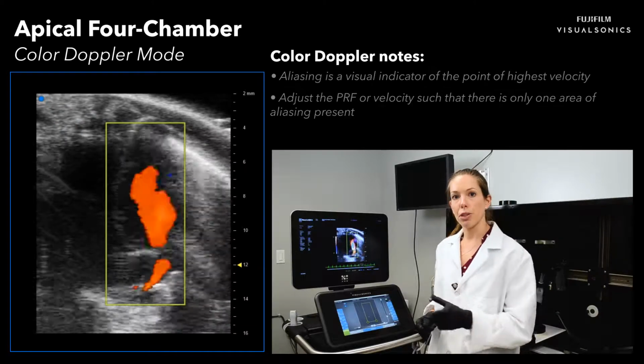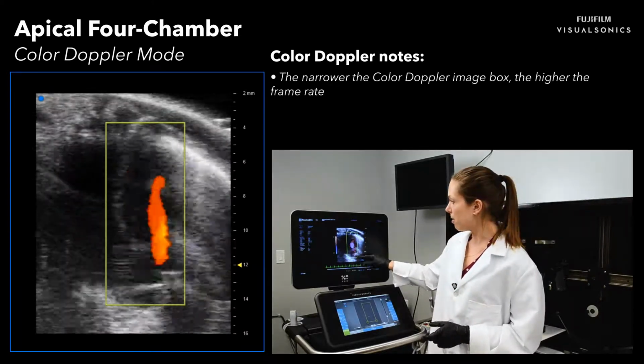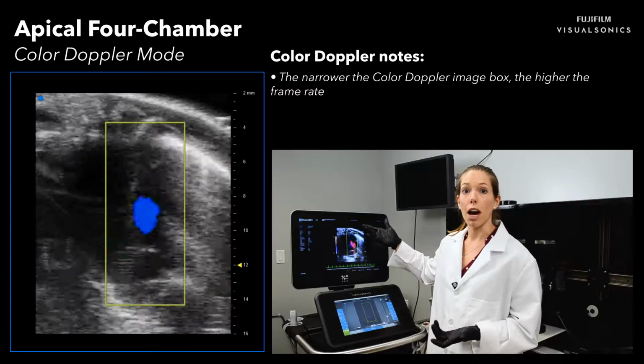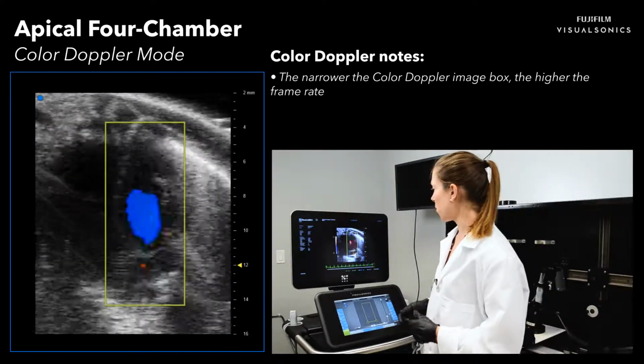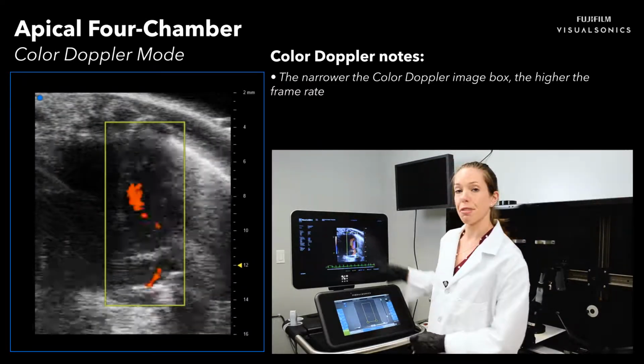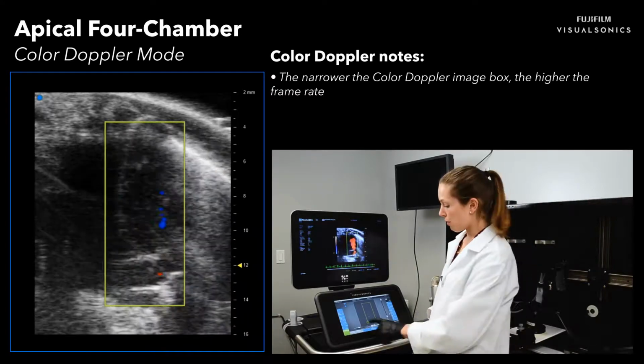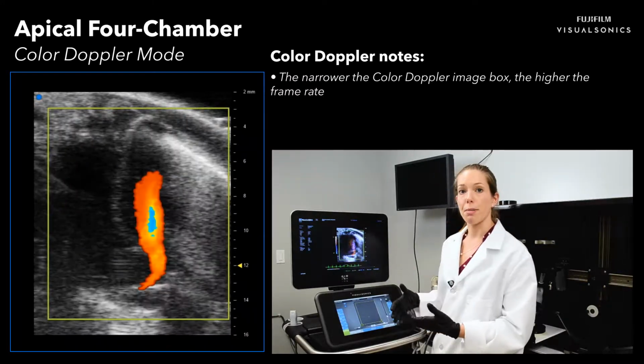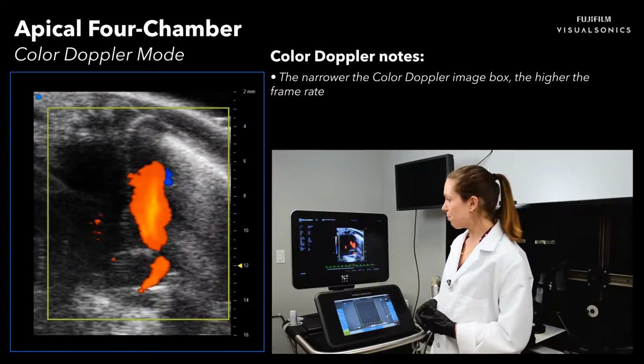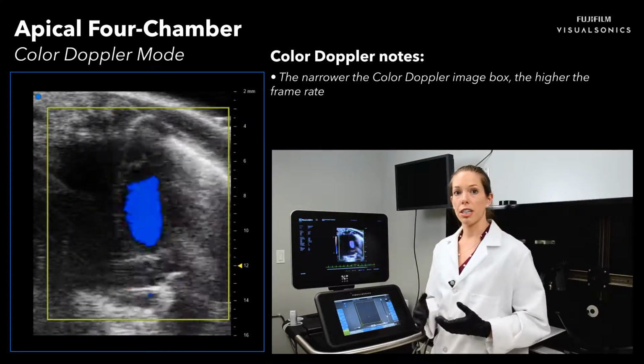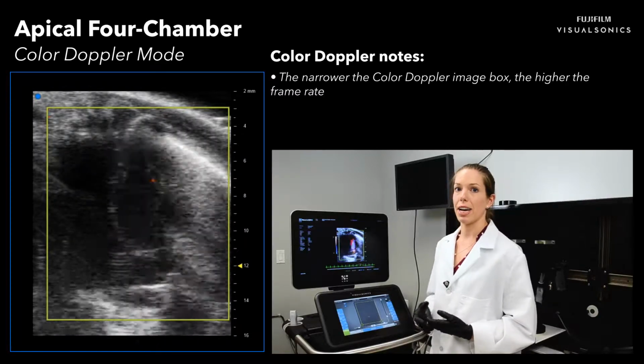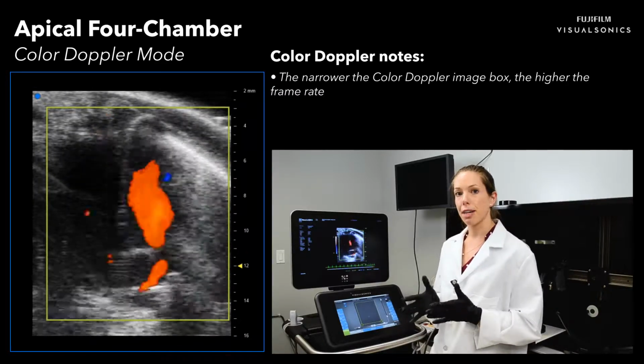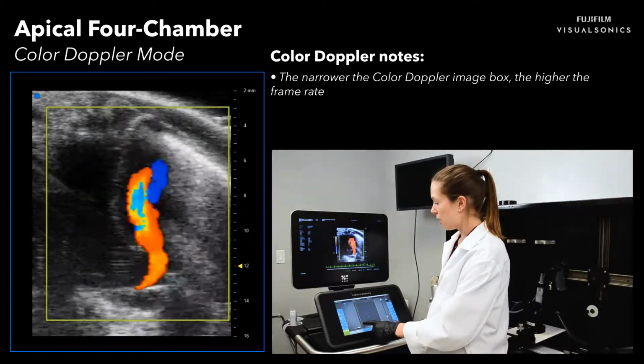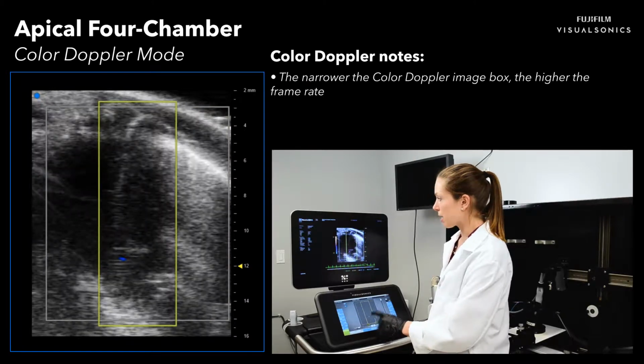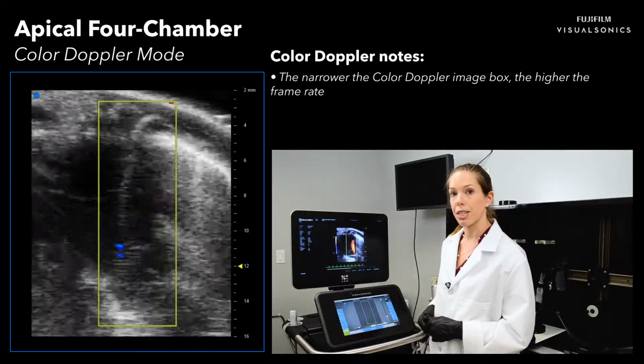I also want to make sure that my color box is narrow and the height is wide. What I'm looking for is a high frame rate for the color Doppler signal. If I make the box really wide, then I'm going to lower the frame rate of the color signal. And since we're imaging in the heart, especially a mouse heart that beats so fast, we want a very high frame rate so we can follow the image on the screen. So I really do want this box to be very narrow, so I increase that frame rate.